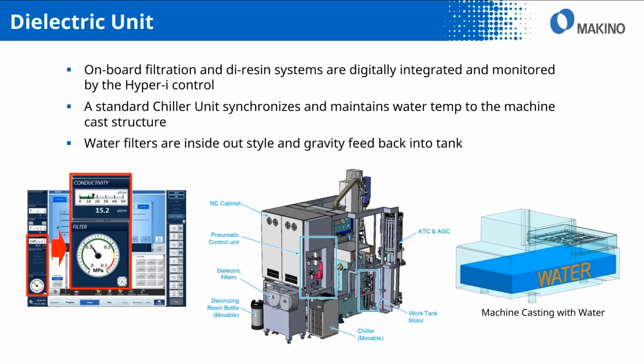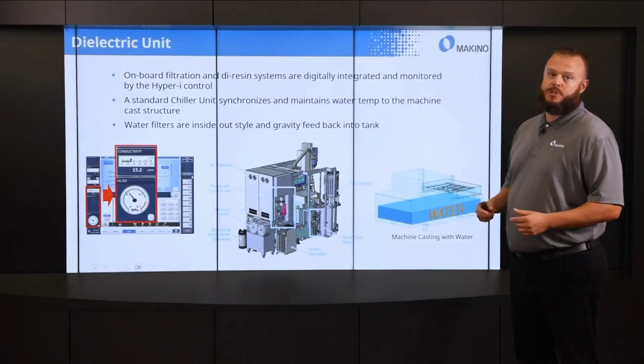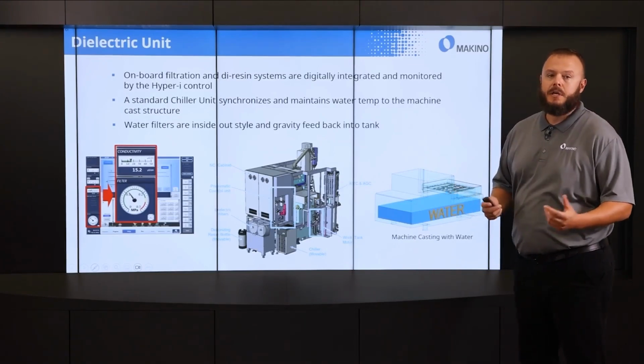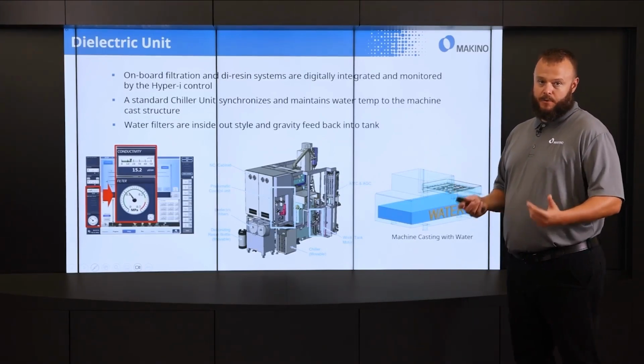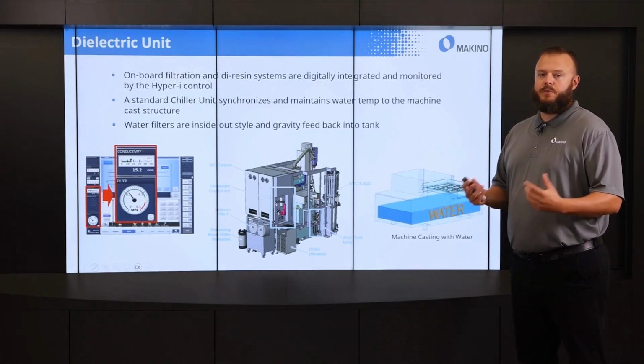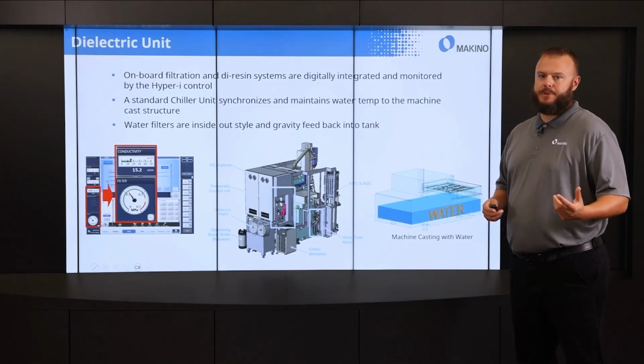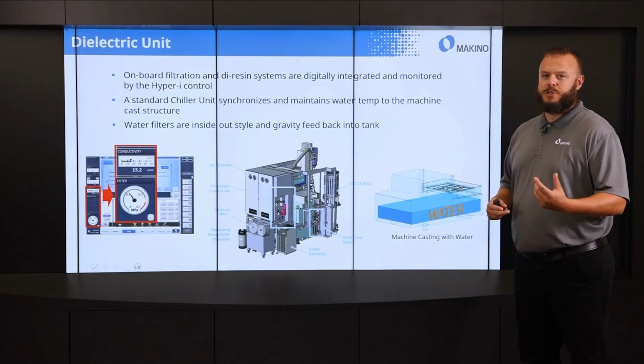We're also always monitoring filter pressure. So this is the back pressure. Whenever we're in the green, the filters are good. Once we get up into the yellow, we'll throw out a warning that informs the operator that it's about time to change the filters. And then once it gets into the red, the machine will alarm out and filters need to be changed. As you can see in the picture on the right, which is just a representation of the machine casting, we use the casting as a holding tank for water. And since the water is always moving through the chiller, which follows the ambient temperature of your facility, it really helps control any machine movement that may affect accuracy.